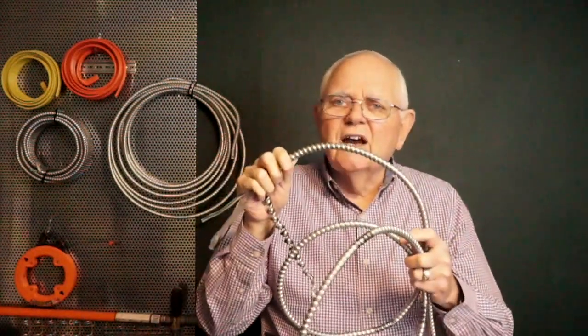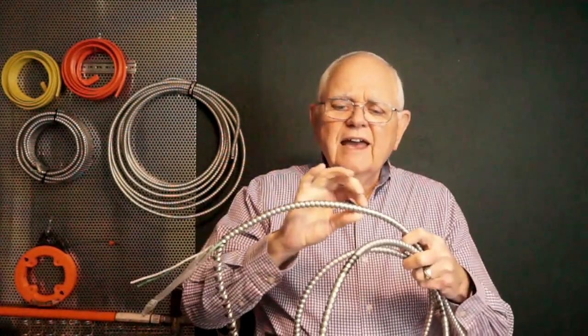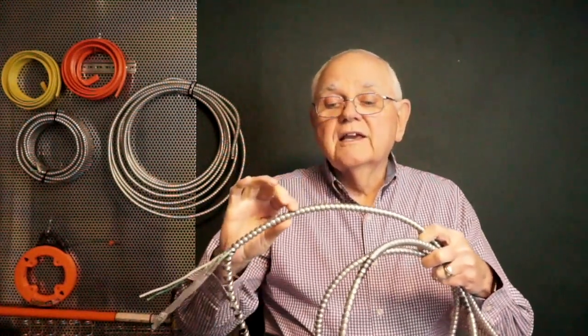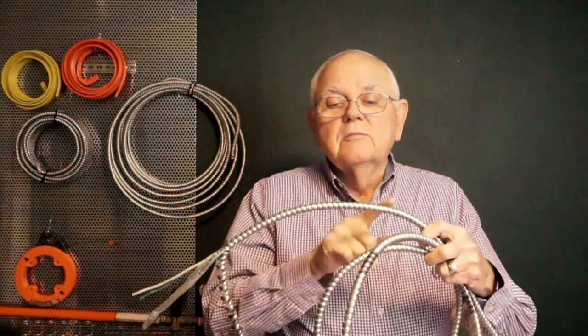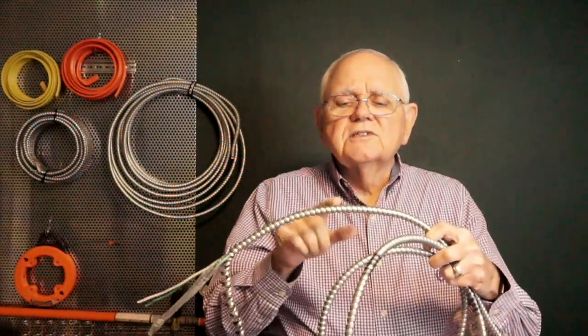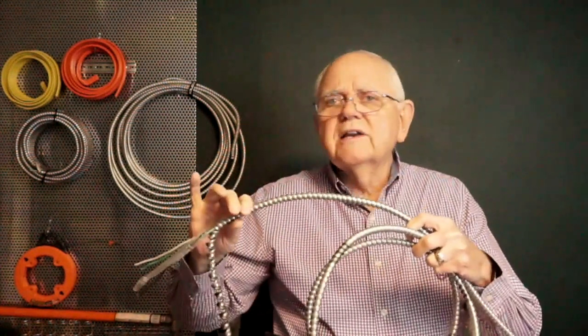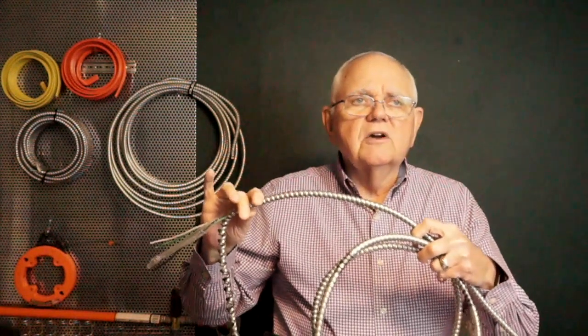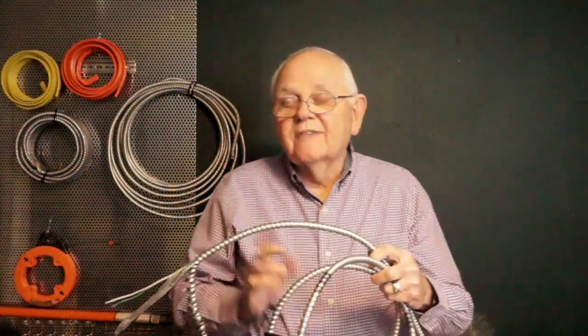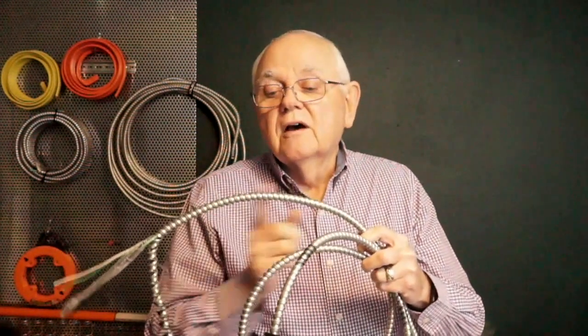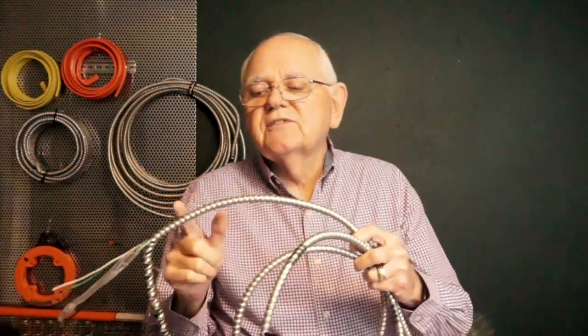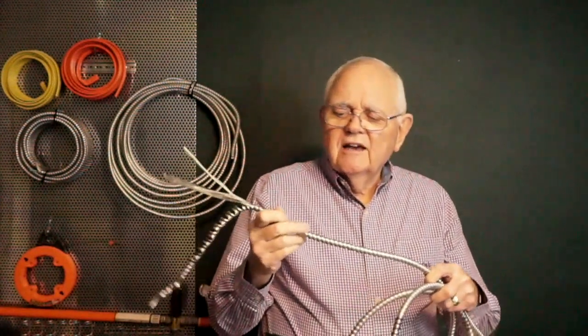In fact, right away, if you think about it, I bet I don't want to take this interlocking metal tape type and put it out in a wet location, huh? But what if I had the corrugated type that looks very much like this, as I said, but it's continuous, so I can't break it open. So it's solid the whole way down. Well, that might be good where I'm going to have it exposed to some moisture or maybe gases and vapors or something like that. So we'll talk a little more about that. In fact, we can also, if we wanted to, well, the manufacturer would put a polymer sheath over the outside, PVC type sheath, and that would give it some different properties.